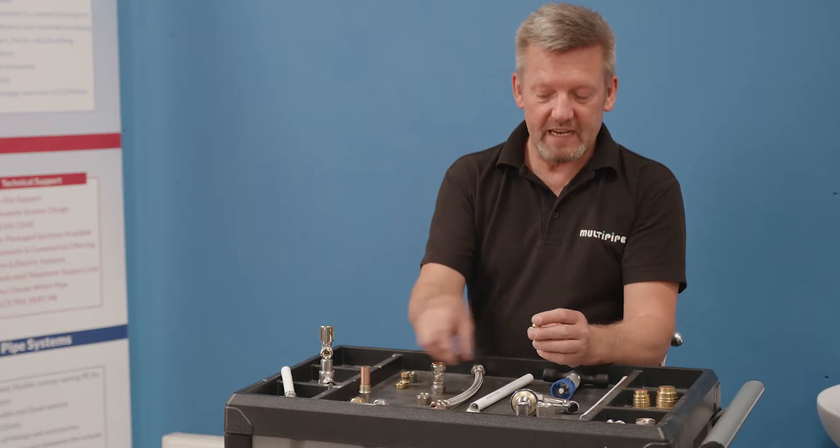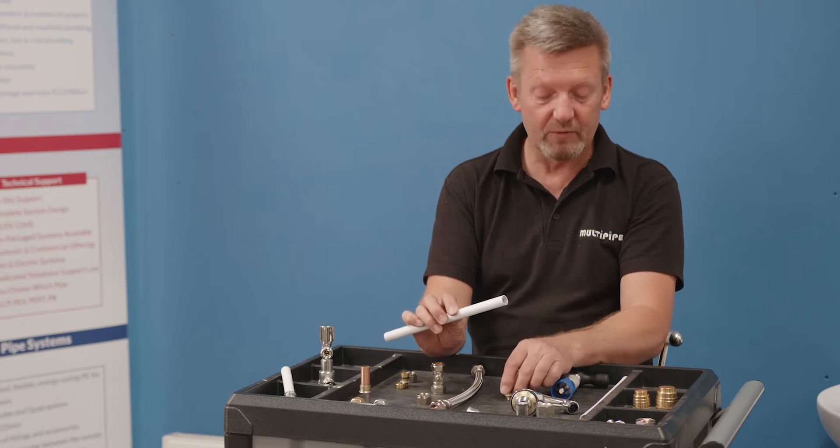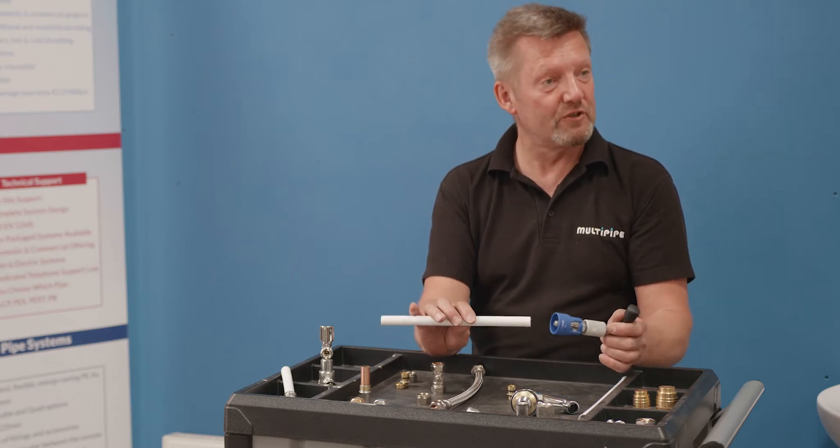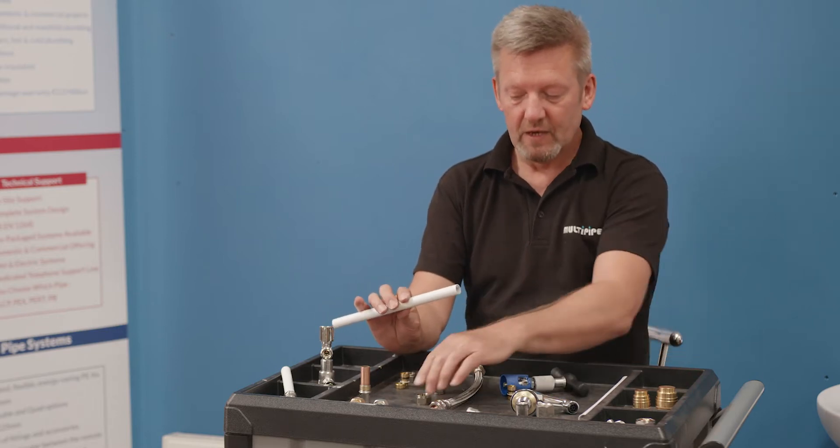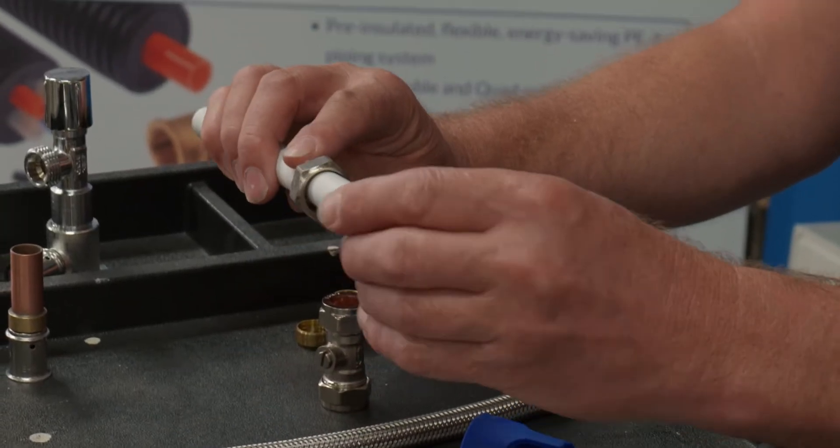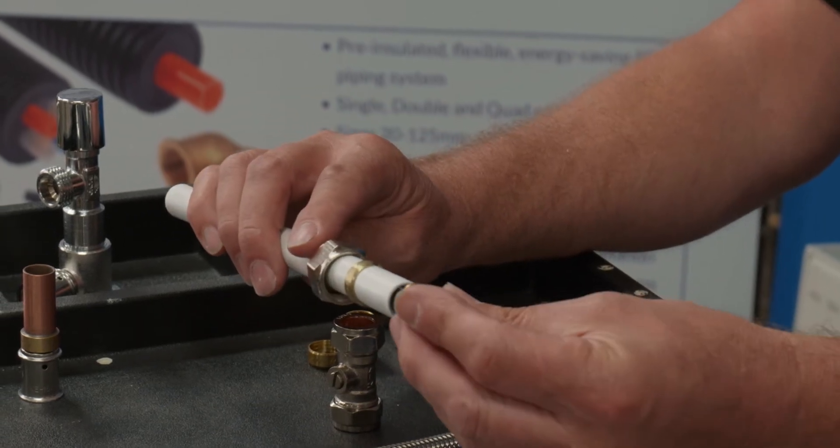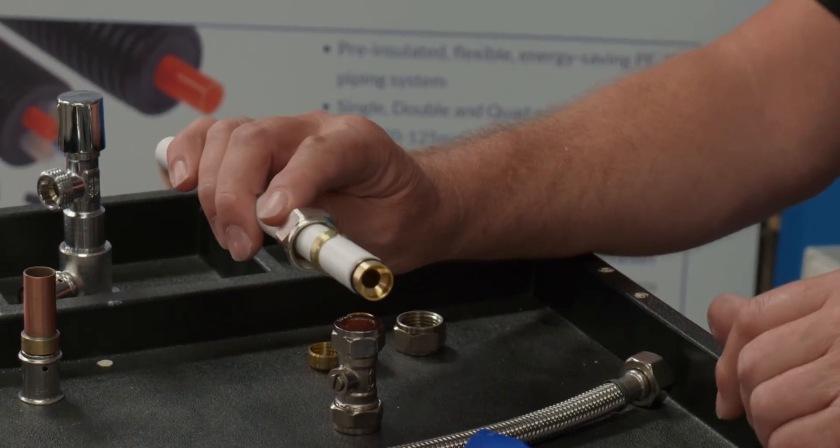And all you do then is with your 16mm MLC, you'll cut and bevel it and prepare it like you would normally do using a traditional beveling tool. Pop the nut on, slip the olive on, not directional so it doesn't matter which way it goes round.